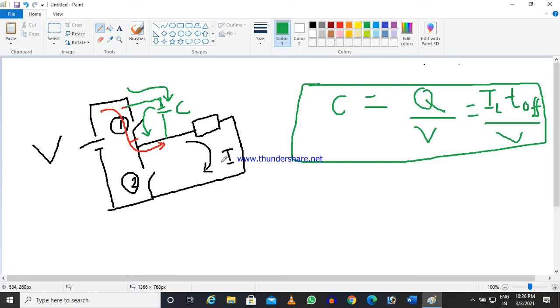So that's why any transistor or IGBT will have a short rating. That means the continuous rating is, say, 10 ampere, but it can take 30 ampere for 1 second. For example, I am just telling, for example. So that is the short rating. From the data sheet of the transistor, you have to find out the short rating of the device.